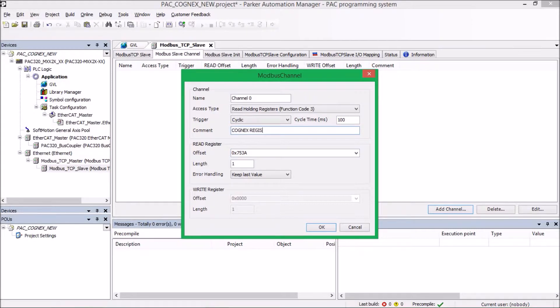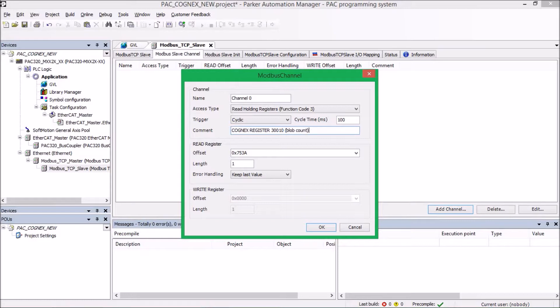So that is going to be stored at holding register 30,010. So in hexadecimal, that's 753A. You can see that's what I set as my offset. And I'm just going to go ahead and add a comment here so I know what it is in my program. And it's going to be blob count. And once I'm finished with that, I can hit OK.